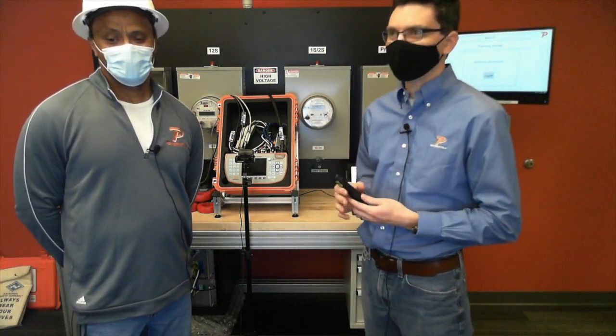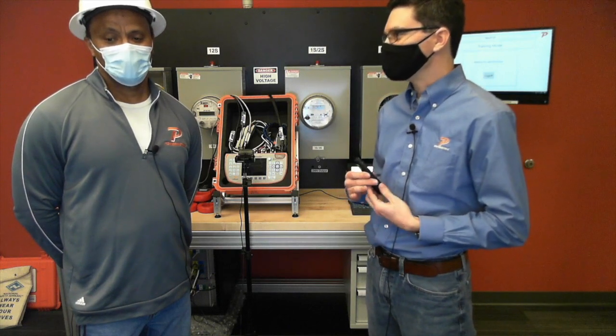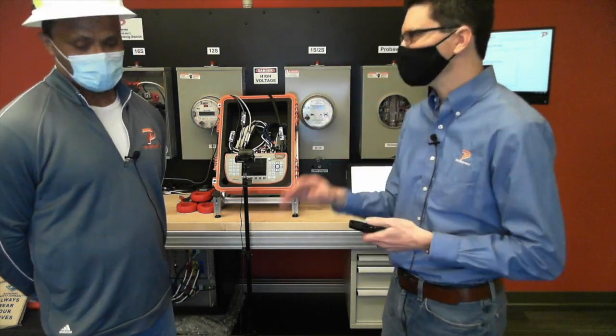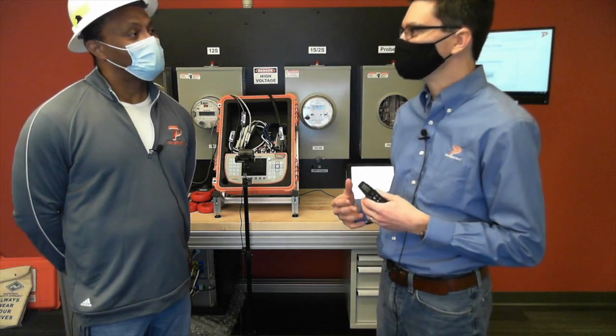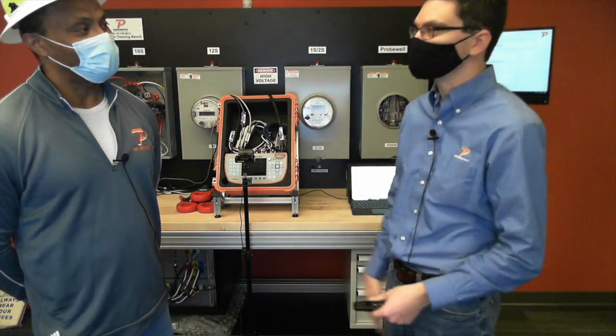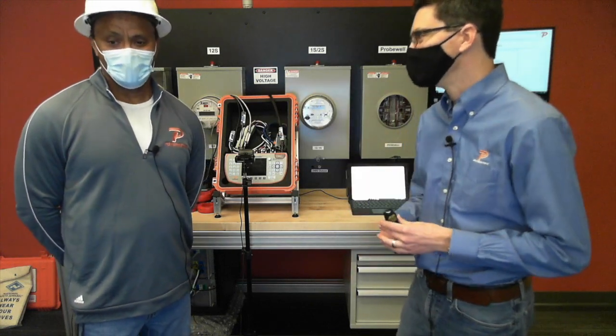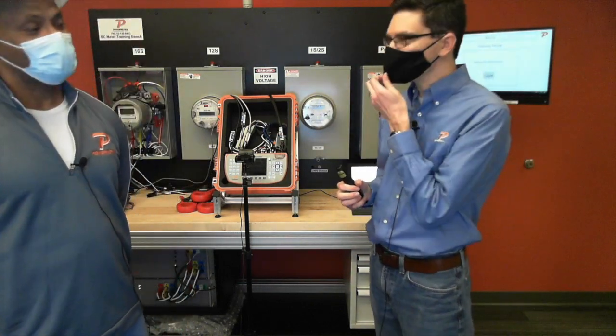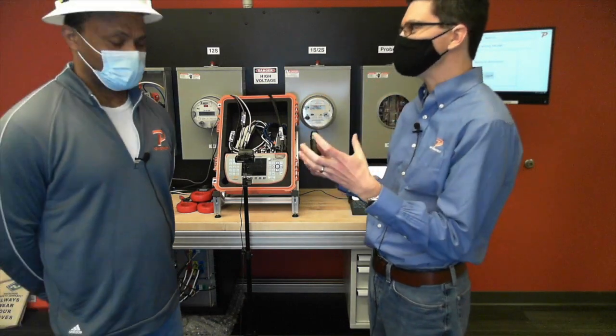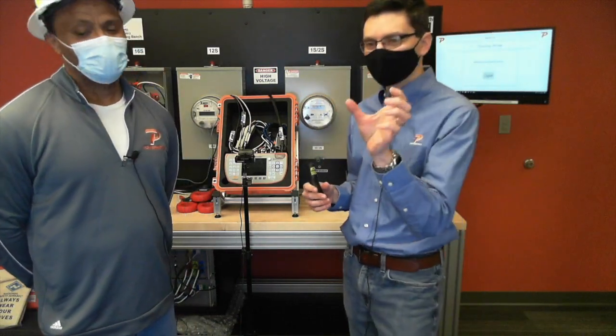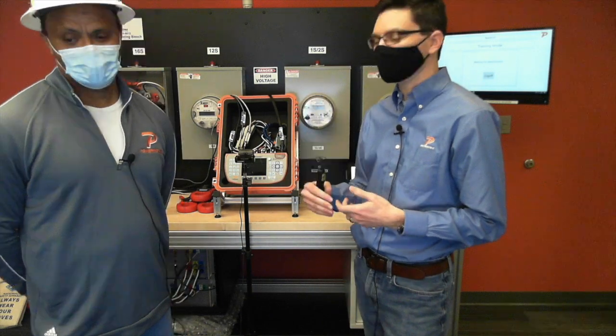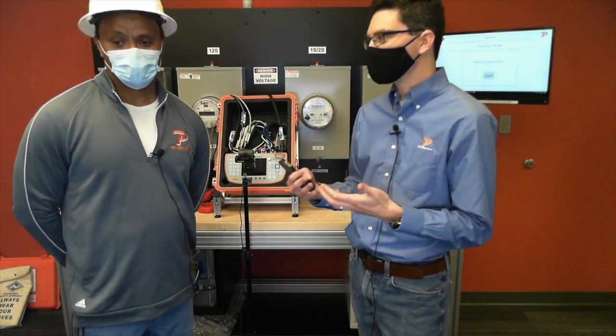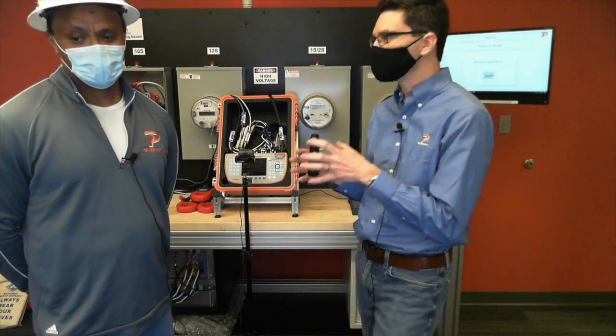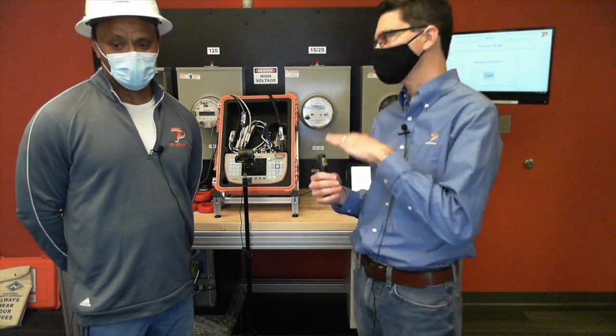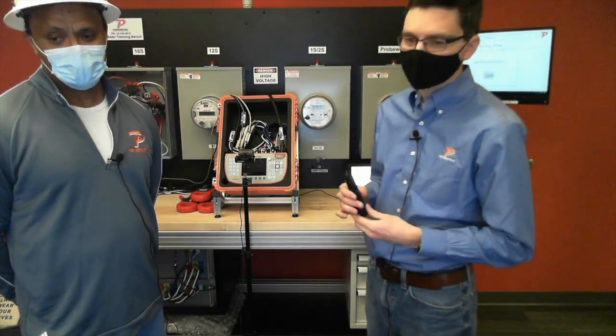They had an AMI project come through about 4 or 5 years ago, and during that time they had to upgrade their K-bases. So what do you think they did? They went with adapters. The adapter basically converted it almost to a CT-rated site. They put split-core CTs on the K-base bars to step the current down, because those 320, 400 amp meter services, the meter couldn't handle that directly, so they had to step it down to something more realistic.